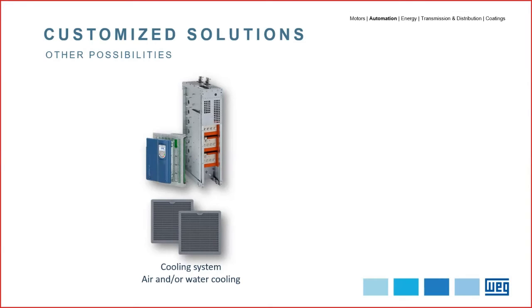A water-cooled panel option, with a cooling system of air and/or water cooling. So a water-cooled panel option for higher current ratings and smaller enclosure. It can also reduce the cost with the HVAC system of the electrical room. There is also the possibility to design a redundant air cooling system, avoiding the overheating of the panel in case of failure of a part of the main cooling system.